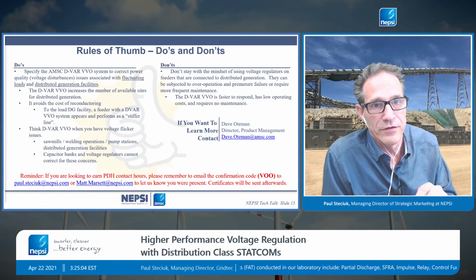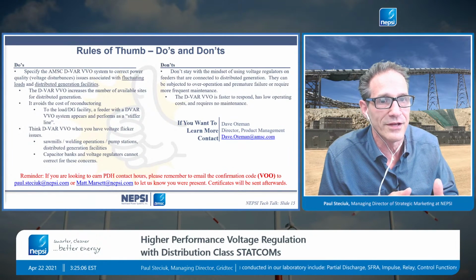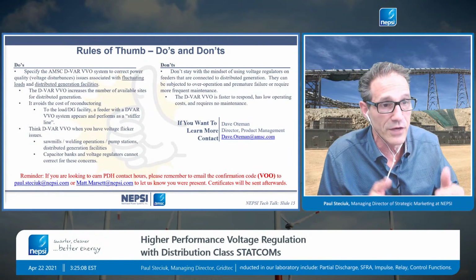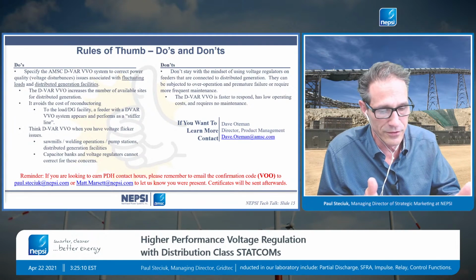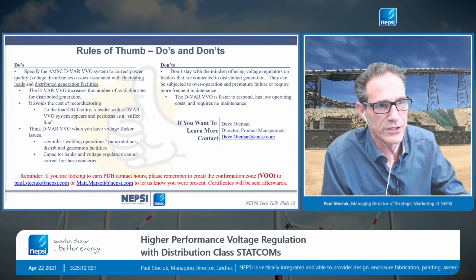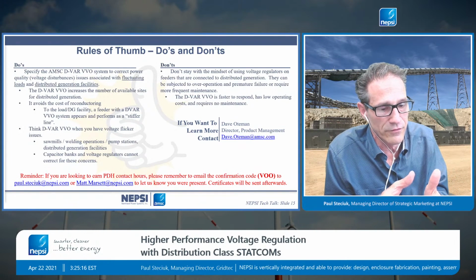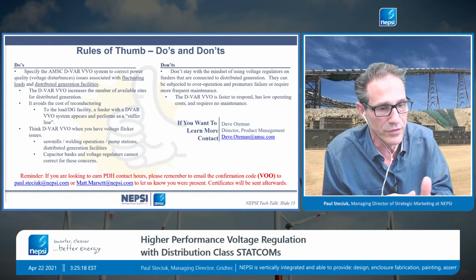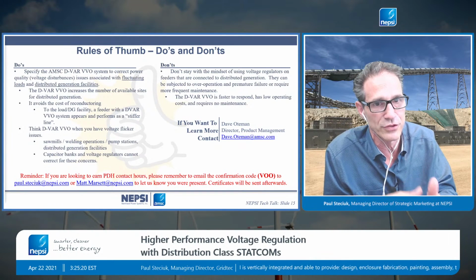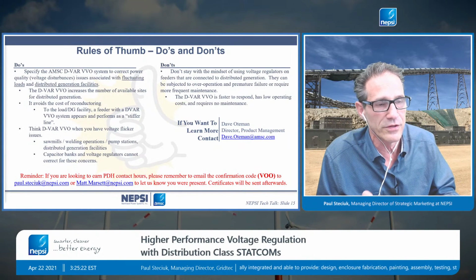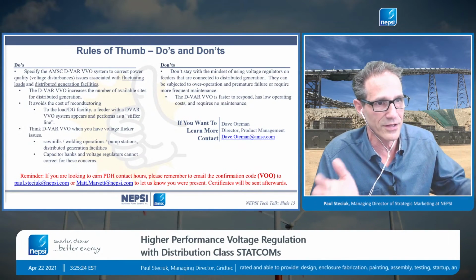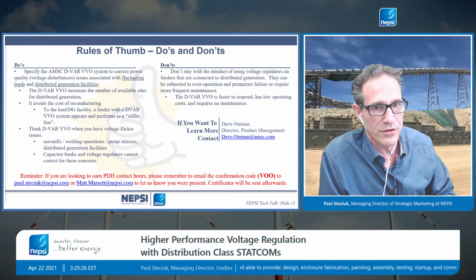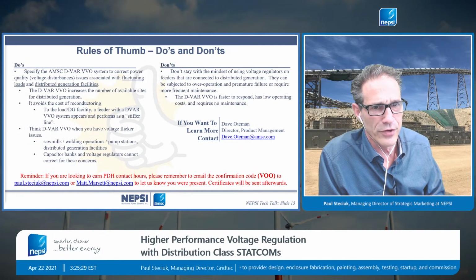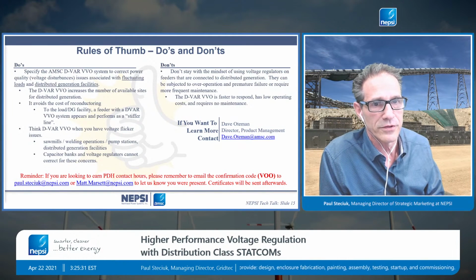The D-VAR VVO increases the number of available sites for distributed generation. If a utility is looking to install renewable generation within a distribution feeder, right now without the VVO system, with the system relatively weak, they have a limited number of choices. With the D-VAR VVO system, you extend the range for installing distributed generation, increasing the number of possibilities.